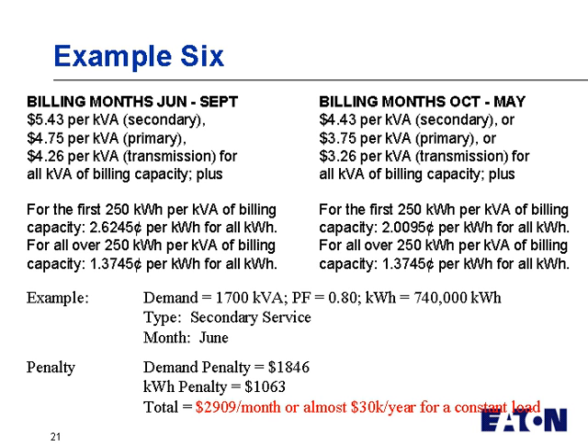Now, finally, this sixth example is probably one of the more detailed ones that is out there, and this one actually affects your kilowatts because you're actually being charged kVA demand, which really means anything less than 1.0 power factor is going to cause a power factor penalty. And also, if you see down below, they actually charge your kilowatt hours based on certain levels of kVA. And so your kilowatts are affected, your kVA are affected, and your demand and your kilowatt hours are affected.